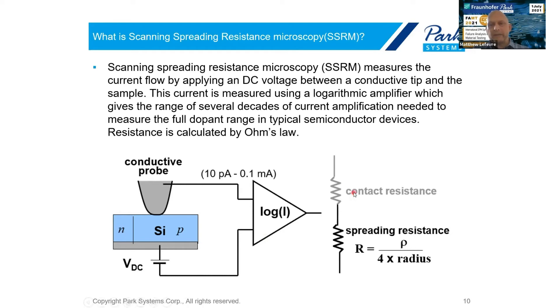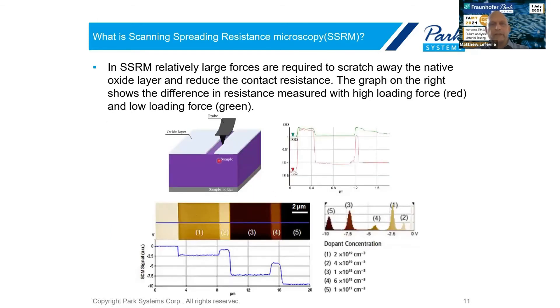It's important to have a lot of force between the tip and the sample, because what we typically want to do is make the contact resistance between the tip and the sample negligible, so that we're only measuring the spreading resistance, which is a function of the resistivity of the sample and the area of contact. We need relatively high force to scratch away any native oxide surfaces, especially on silicon. We can see in red the curve with high force, where we're able to greatly reduce the resistance we encounter, opposed to lighter scanning shown in green. We also see a doping level staircase here, going from 10 to the 19th down to 10 to the 17th with very clear structures. Importantly, in SSRM as opposed to SCM, we're more sensitive to higher doping concentrations than to lower doping concentrations.